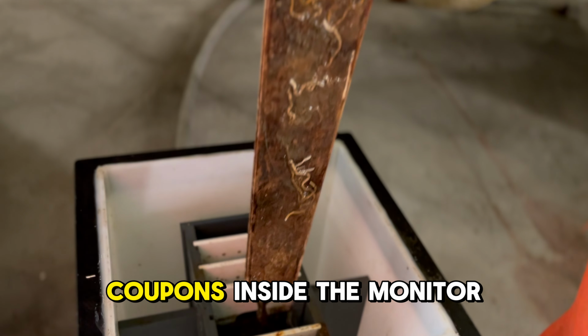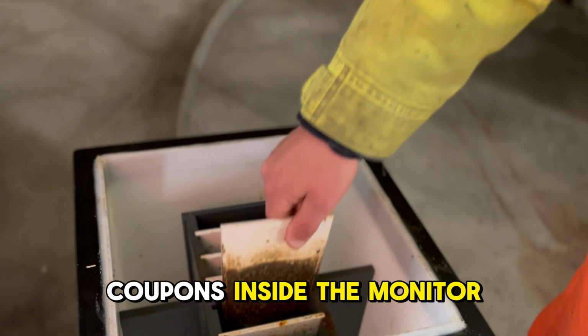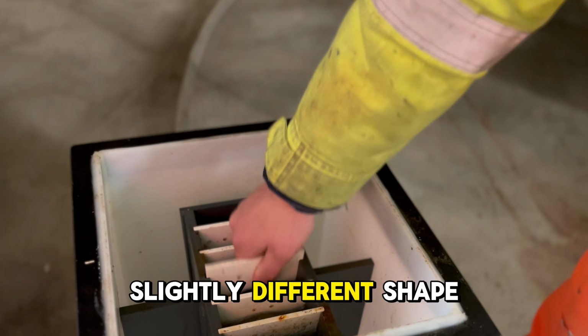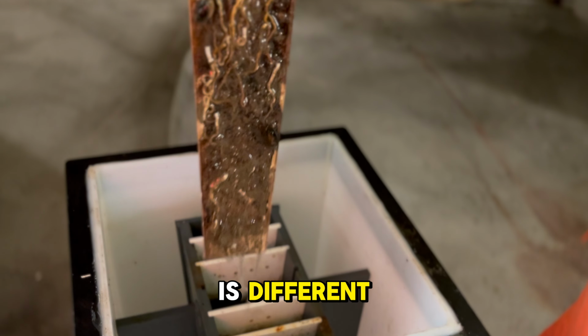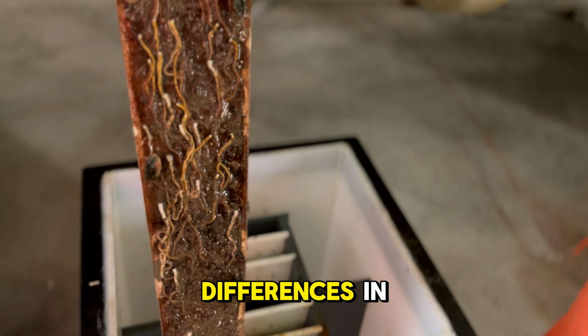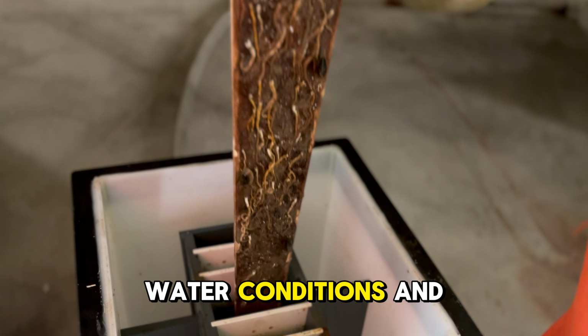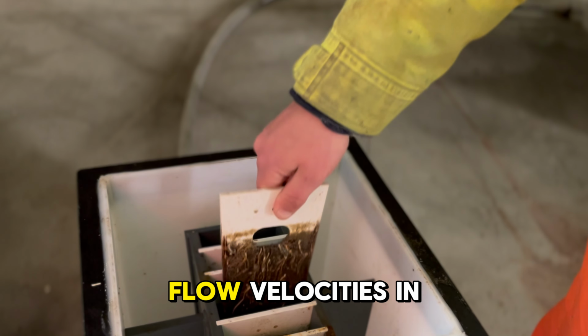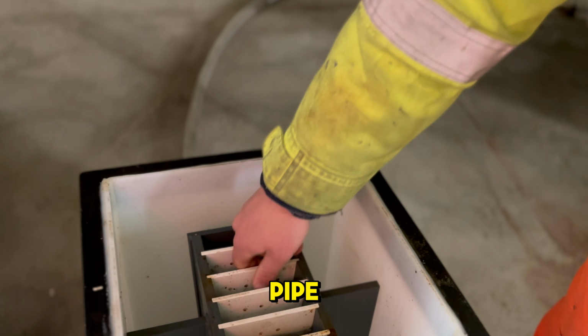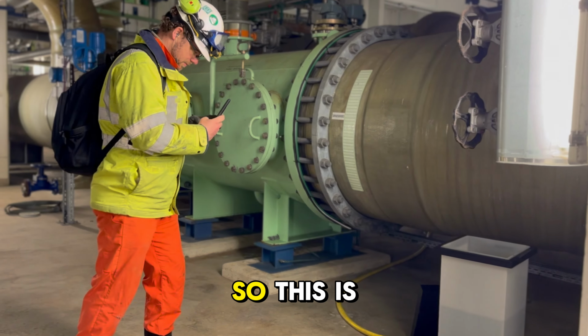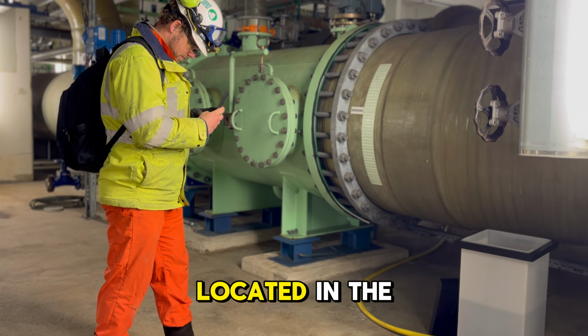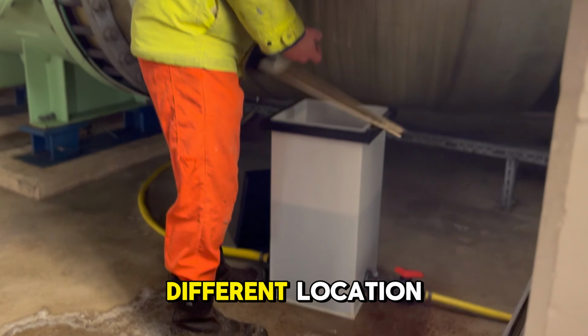There are 5 coupons inside the monitor, and each has a slightly different shape, and the turbulence is different, which mimics the differences in water conditions, turbulences and flow velocities in the cooling water pipe and in the cooling water system in general. So this is another Biovision monitor located in the same plant but in a different location.